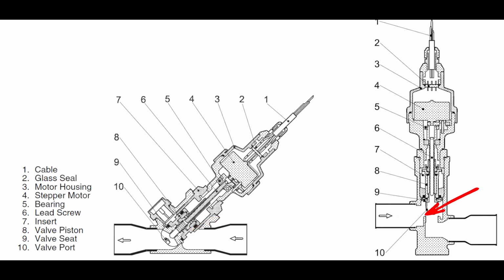The other way this has been done is the bottom of the plunger will have a stem, and the plunger may seat up here, but the sight glass will be down here. What we're looking for is where that stem falls in position. If the stem is far up in the glass, the valve is open to some degree, and if the stem is down towards the bottom, that's typically an indication that the valve has closed. This is going to be critical when it comes time for calibration and plunger testing. So the sight glass is a critical part of these valves and our ability to troubleshoot and test them effectively.